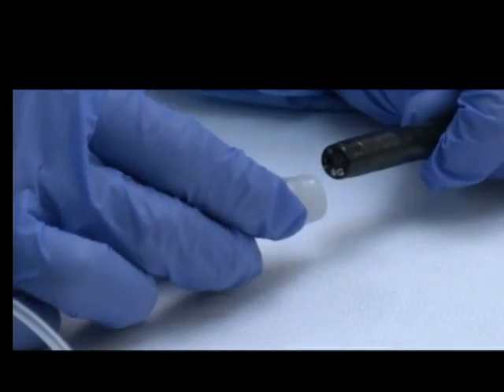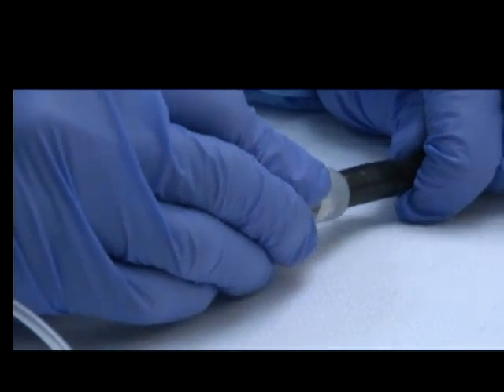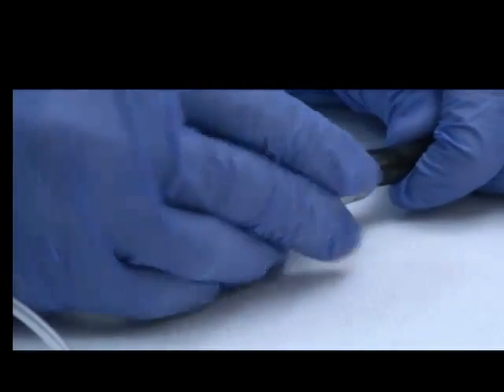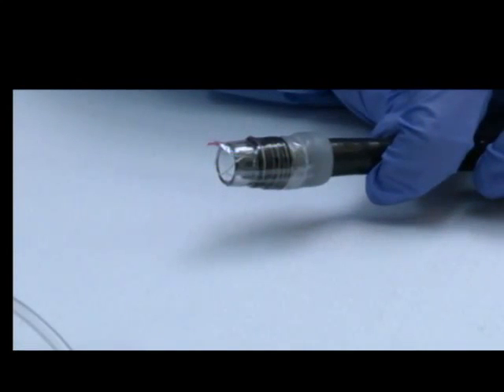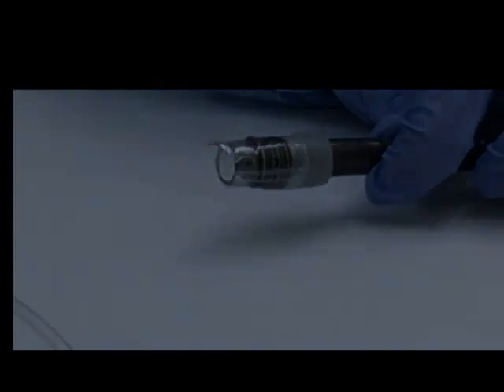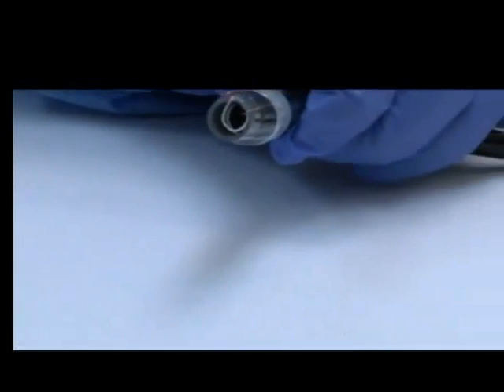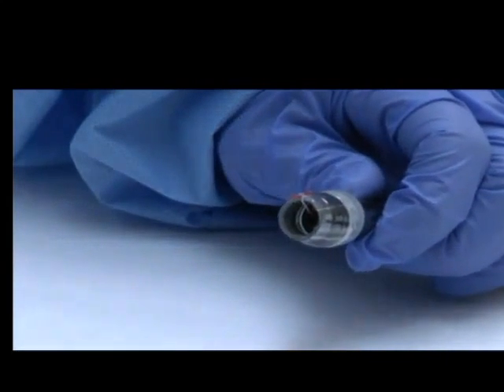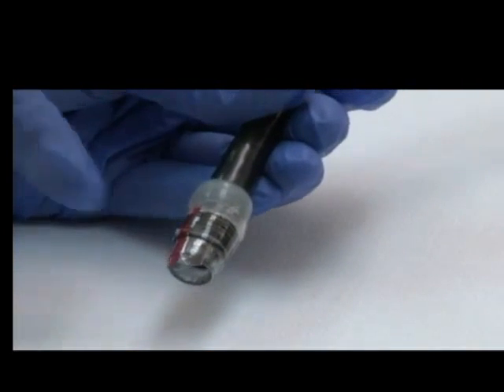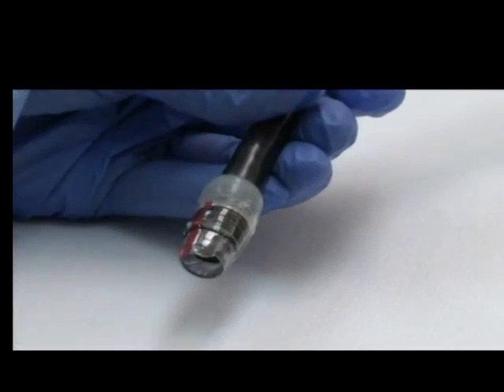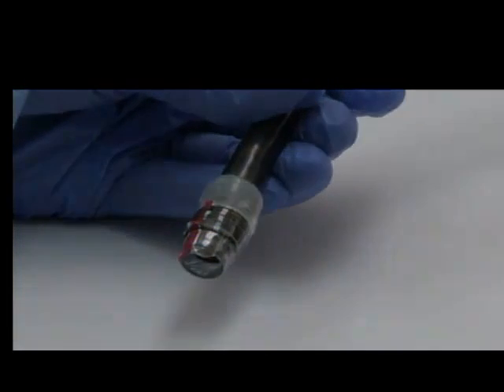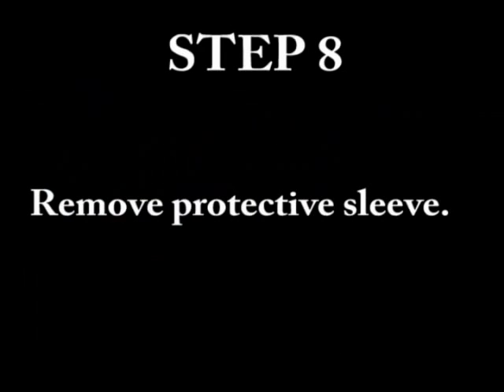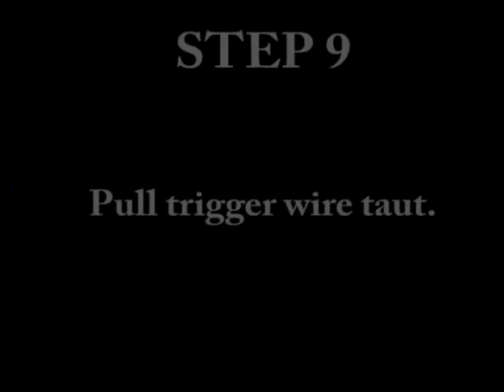Align the red stripe on the band barrel with the biopsy channel. Advance the soft portion of the band barrel onto the endoscope. Continue advancing until the plastic portion of the band barrel contacts the distal end of the endoscope. The scope should occupy approximately 1/2 of the barrel. Remove the red tearaway strip and peel away the protective plastic sleeve on the band barrel.